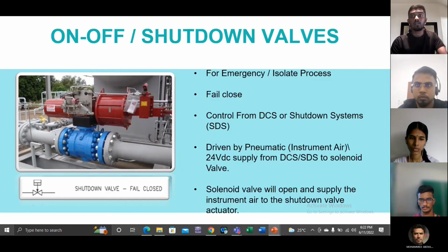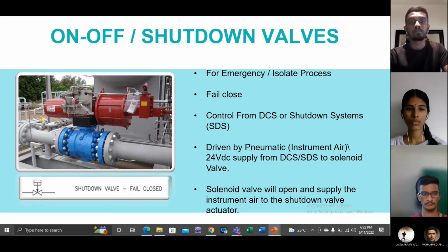Okay, on and off shutdown valves. These can be found in many places. They are for emergency, to isolate the process, for fail close, controlled from DCS or shutdown system, driven by pneumatic instrument air. It has a 24 volt DC supply from DCS or SDS to the solenoid valve. The solenoid valve will open and supply the instrument air to the shutdown valve actuator.